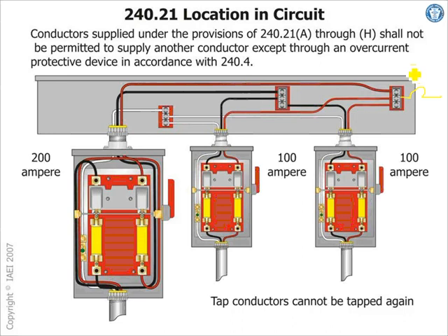what would this be to meet the code, the maximum? This can be 10 times 100. This can be 1,000 amp maximum here, right? You guys see why? There's 100 amp here times 10. If these are the 10-foot rule, I'm taking it 10 feet. Let's just say this is 25 foot.